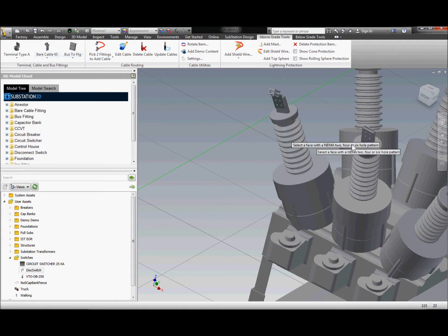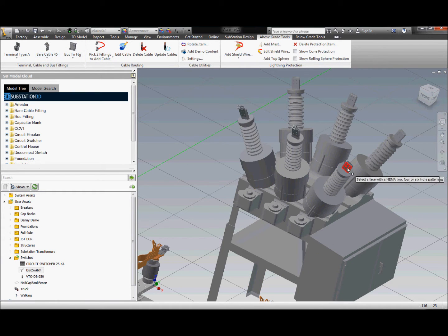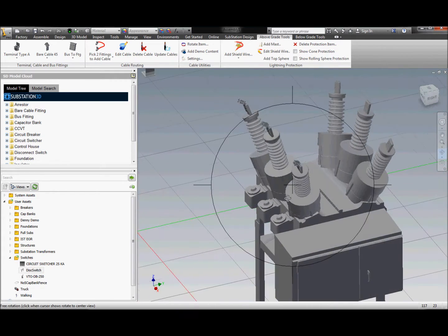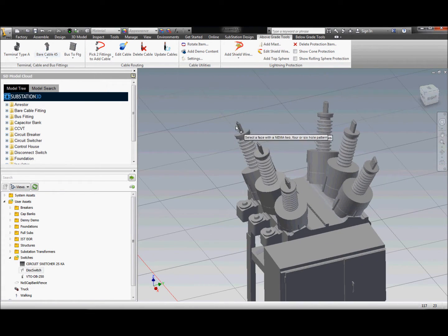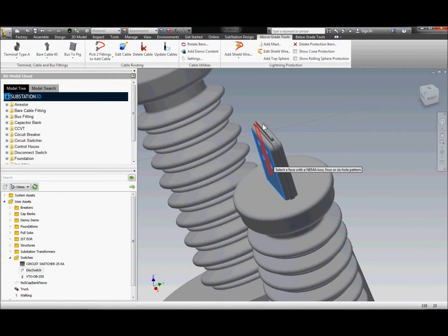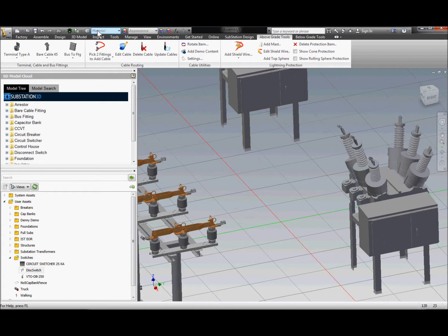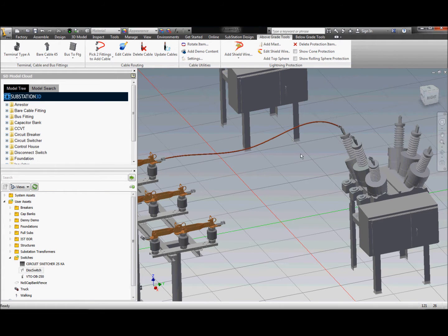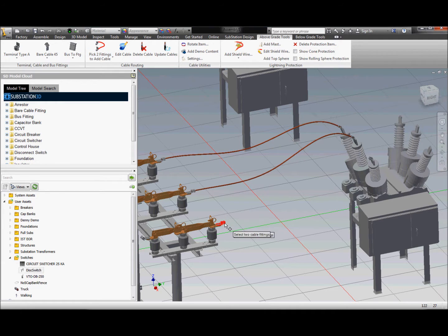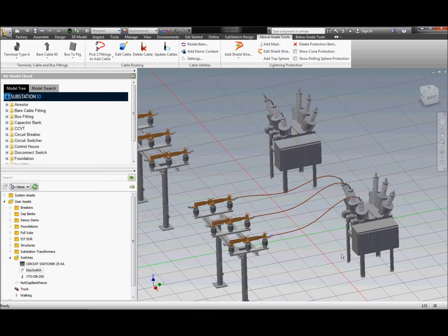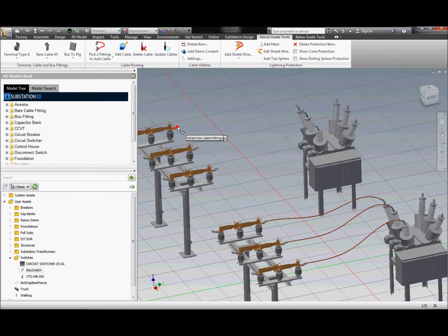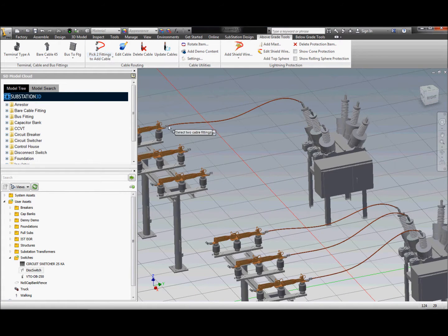Going to the substation menu, the above-grade tools show some bare fittings — cable fittings that we can put into place. Here we're just picking some surface information; we don't need to pre-define anything in those parts. A lot of these files come in as STEP files directly from vendors — we just drop those in place and snap some fittings to them. The disconnect switch already had some fittings; we've just placed some fittings on the breaker. To run some bare cable, we use the 'pick two fittings' cable feature inside the substation tool, and it's going to automatically create the 3D spline of the cable, calculating the best values it can for SAG. This eliminates a lot of different picks and clicks that you'd have to do within the 3D modeling tool itself.